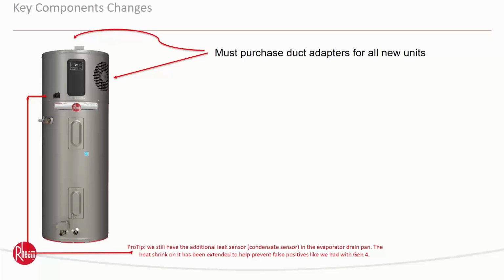We do have a leak sensor, or a sensor for the condensate, up in the top there, so that if there's an issue with that condensate, it's not draining. You do have to run a drain off the condensate with the heat pump water heater, and if it's not draining or has a problem, it's going to shut the heat pump down and notify you.